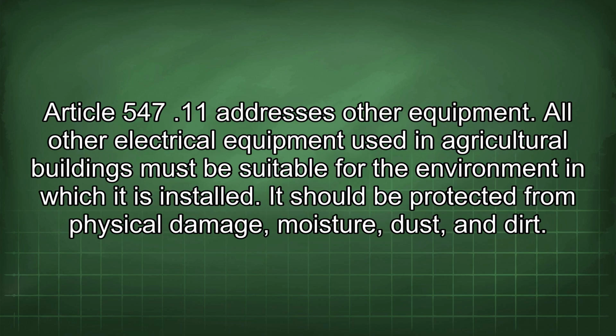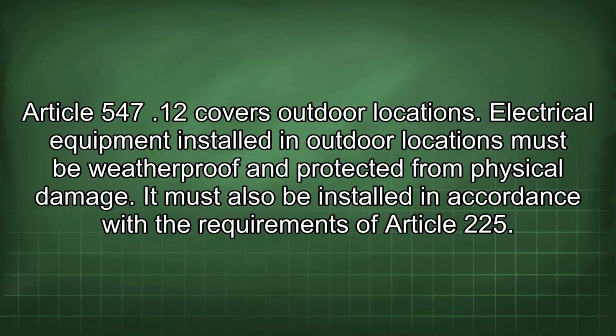Article 547(11) addresses other equipment. All other electrical equipment used in agricultural buildings must be suitable for the environment in which it is installed. It should be protected from physical damage, moisture, dust, and dirt. Article 547(12) covers outdoor locations. Electrical equipment installed in outdoor locations must be weatherproof and protected from physical damage. It must also be installed in accordance with the requirements of Article 225.